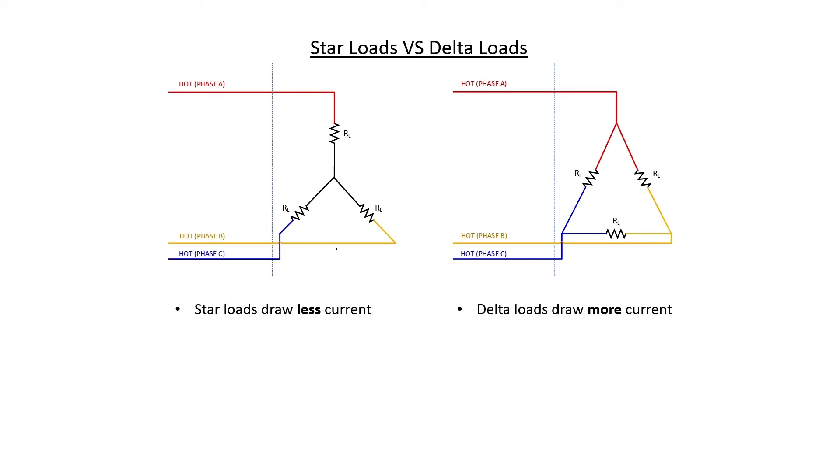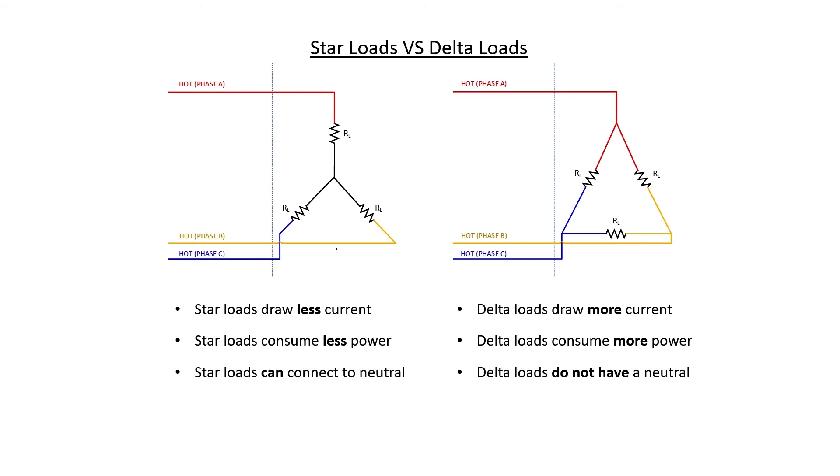Let's now summarize the differences between star and delta connected loads. First of all, star loads draw less current because they have a lower voltage from phase to neutral. Delta loads draw more current because each load sees higher voltage. Star loads consume less power because at a lower voltage, you have a smaller V squared over R. Delta loads, on the other hand, consume more power. Star loads can connect neutral. A neutral point in a star load is also quite commonly connected to the Earth. Delta loads don't have a neutral at all. They will, however, still have an Earth that's typically connected to the case for safety reasons. It's not shown here on the circuit, but earthing is, of course, very important in any sort of industrial electrical power installation.